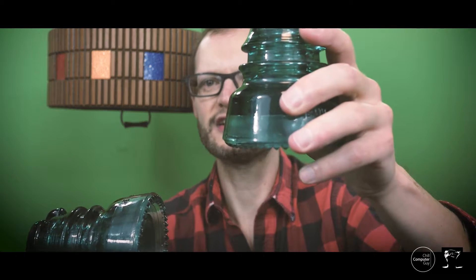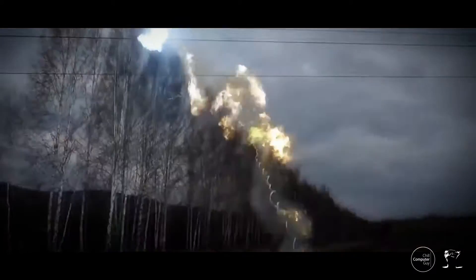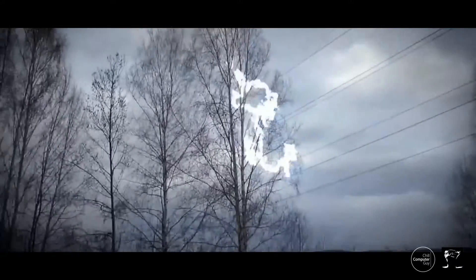So these things are very, very important. You can always tell if you have a distribution, supply, or transmission line by the distance of the three wires. Distribution line wires are pretty close. A supply line, which is normally about 70,000 to 105,000 volts, has wires separated quite a bit more — you'll see a T-section configuration. These insulators are also much bigger, usually about two to three times as long, because with higher voltage the wires need to be farther apart or they'll arc. So if you have a 70,000-volt line, you need to separate those three phases more.